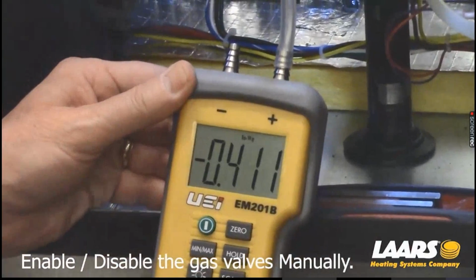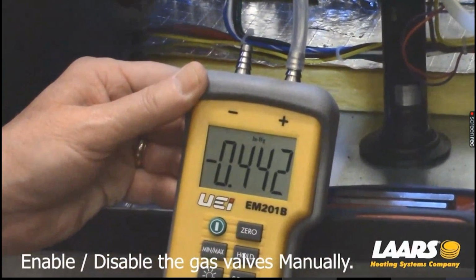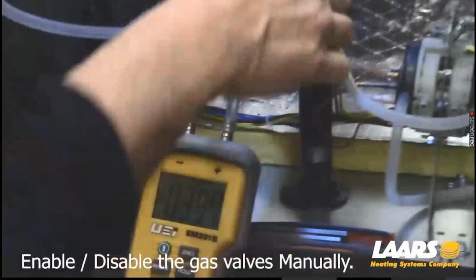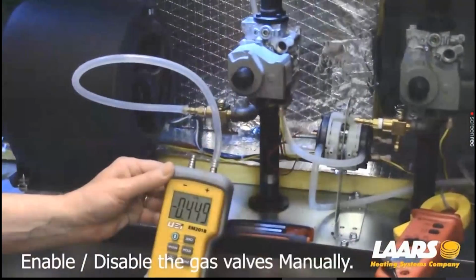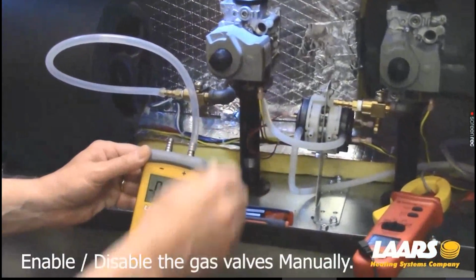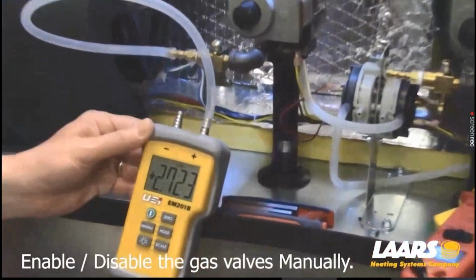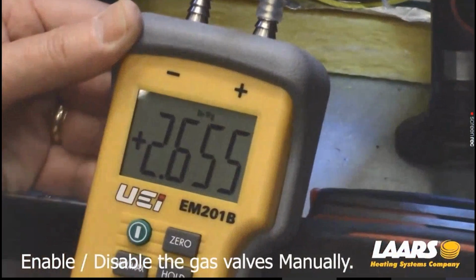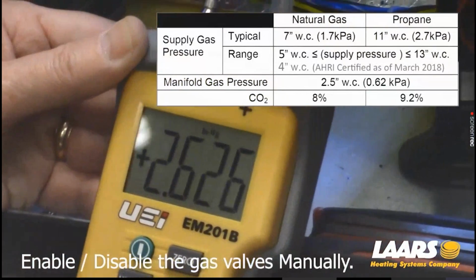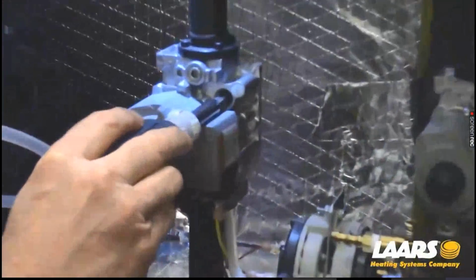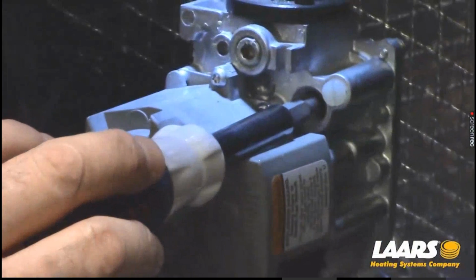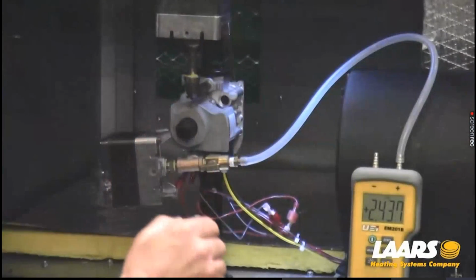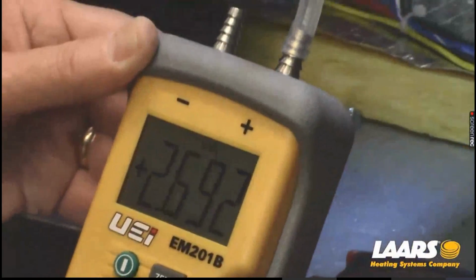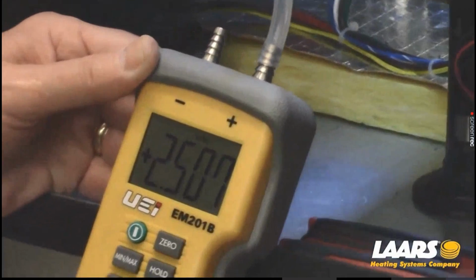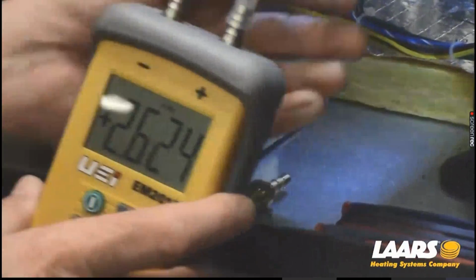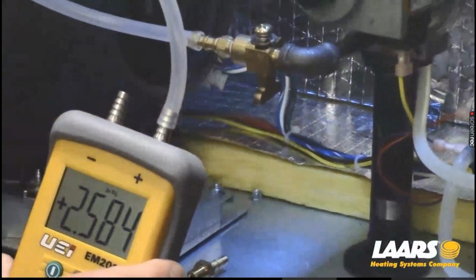Now, you'll see that I'm not reading 2.5. The reason is I shut that gas valve off. What I'm getting is a pressure reading from my burners through the manifold, okay? I will energize my gas valve, and now you'll see I'm reading positive 2.65. In this case, I will go in and I will make a slight adjustment. Now you can see I've set it between 2.4 to 2.5. It's going to bounce around a little bit. Again, it's a couple of tenths, it's not a big issue. Lastly, I'll shut this valve off, and I'll go to my third valve.